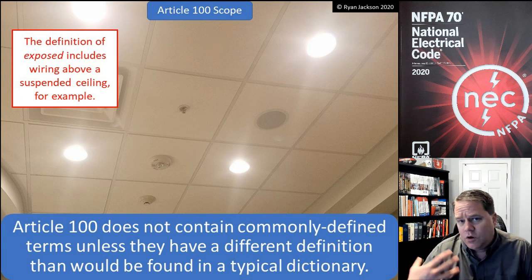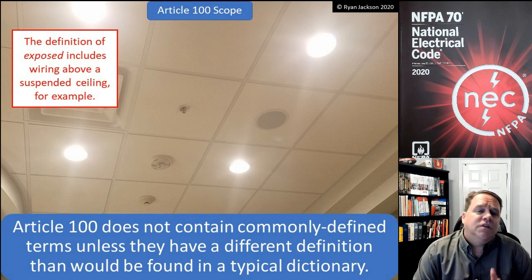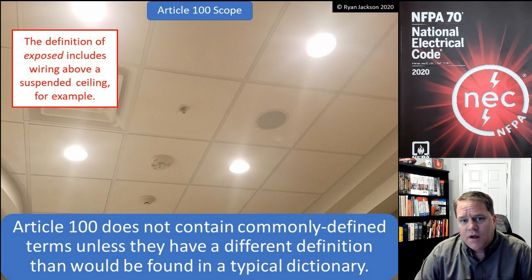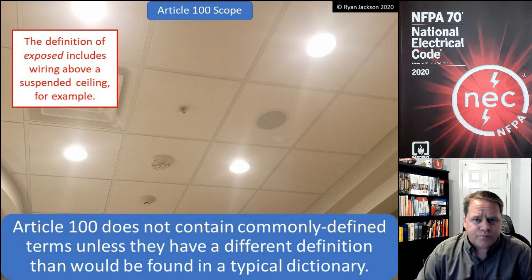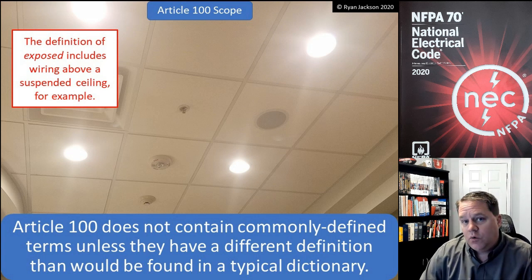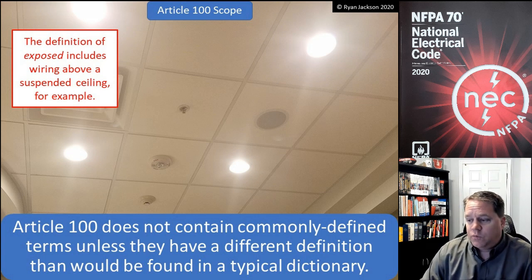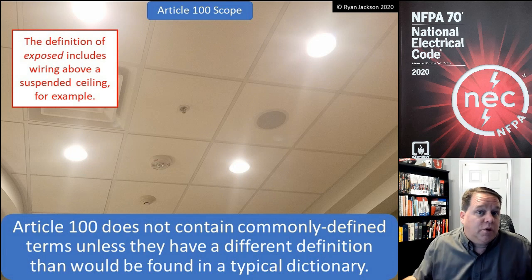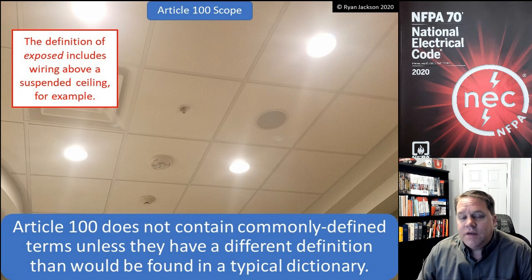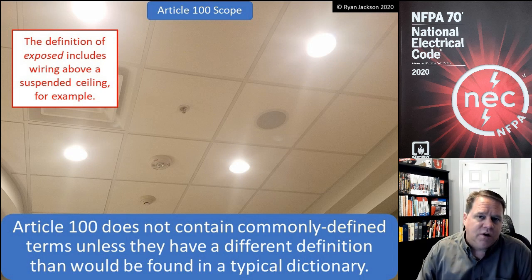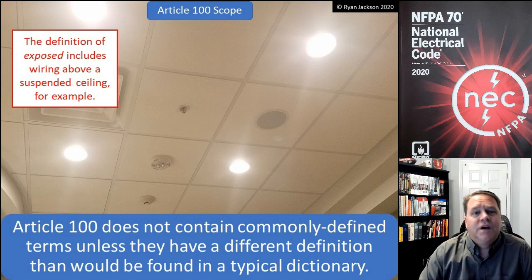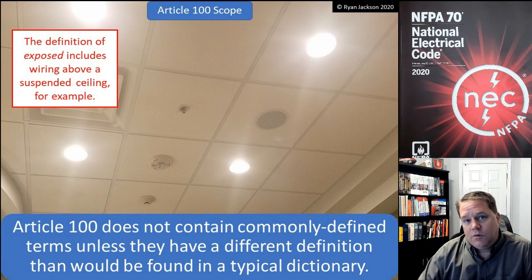But for something like the word "exposed," we have a different definition in the NEC than we would in the rest of the world. Looking at the picture here, wiring above a suspended ceiling is "exposed" in the NEC. If we ask a regular person on the street whether something they cannot see is exposed, the answer would probably be no. So in the NEC we have a different definition of "exposed," and that's why we define the term.